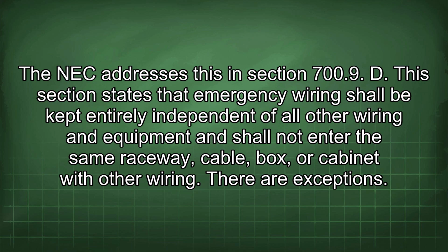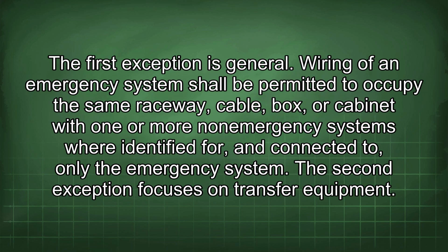The NEC addresses this in section 700.9. This section states that emergency wiring shall be kept entirely independent of all other wiring and equipment, and shall not enter the same raceway, cable, box, or cabinet with other wiring. There are exceptions. The first exception is general. Wiring of an emergency system shall be permitted to occupy the same raceway, cable, box, or cabinet with one or more non-emergency systems identified for, and connected to, only the emergency system.